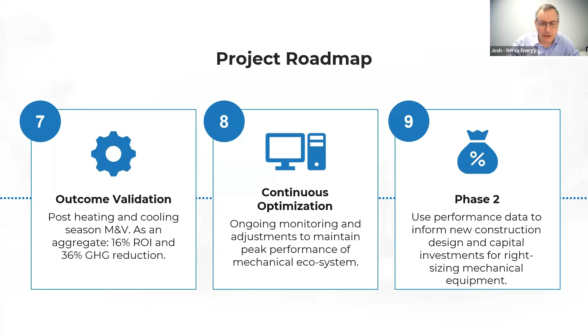And now into phase 2, we're using all this performance data we're collecting in real time to both inform their new construction, where they're already implementing both air source and ground source heat pump systems into some of their new builds, and looking at the retrofit play for their existing buildings about how, in conjunction with mechanical life cycle replacement, they're going to cost effectively implement different types of heat pumps into their existing building portfolio as the end of life of the equipment comes up, so that over the next 20 years they get to maybe not zero carbon operation, but very low carbon operation.